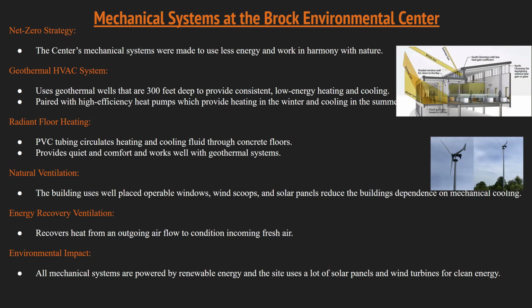The use of natural ventilation in this building is extremely critical to how air and internal temperatures are moved and maintained. There are timed windows at the upper part of the building that open at night, so as the temperature comes down, we're not continually running air conditioning or maintaining a 72-degree internal temp, because we're using wind from the coast to drop the interior temperature by moving warm air out as it rises during the night. So when you walk in the morning, you walk into a nice, cool building. On hotter days you may still need to run some air at night, but most of the year you're able to maintain a relatively comfortable internal temperature through this process.